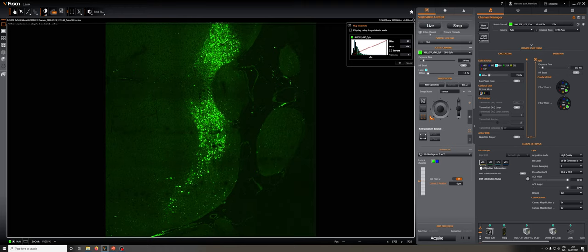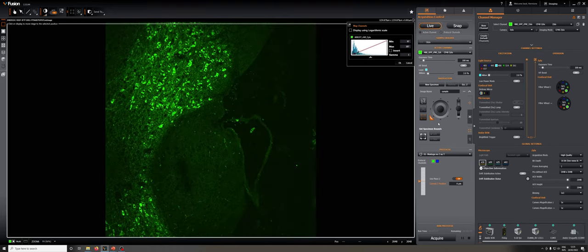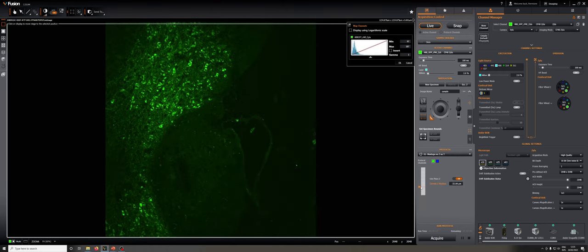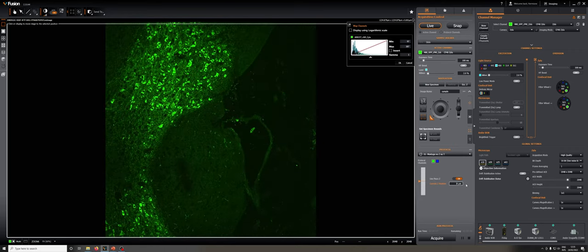If I go back to active channel so we only have one at a time, once we've focused with the focus knob on the microscope, we can start using the piezo — a finer focus mechanism on the system that's independent of the microscope — to move up and down in focus. You'll notice that when you first start the software and grab this, it jumps by about 30 microns. That only happens the very first time. When that happens, just go back to about zero by using the mouse wheel, dragging, or typing zero, and then refocus by eye. This appears to be a bug, and newer versions may not have it. Once reset, moving up and down from zero corresponds to where you left the focus with the microscope knob.